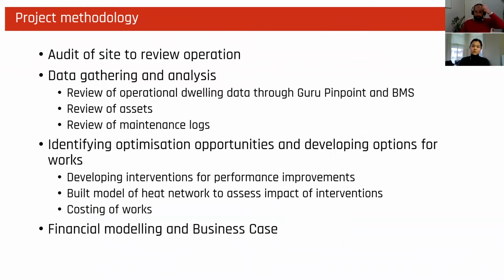The project methodology was that we did an audit of the sites. That's data going to site, going to dwellings, going to the energy centre. It's very important to be hands-on and actually physically see how the networks are working. Then there was a data gathering exercise where we collected operational data from the Guru pinpoint system and from any BMS systems they had on site. We reviewed the assets, the equipment installed, and the maintenance logs. We also interviewed or spoke with O&M contractors to understand what the legacy issues were on that site.